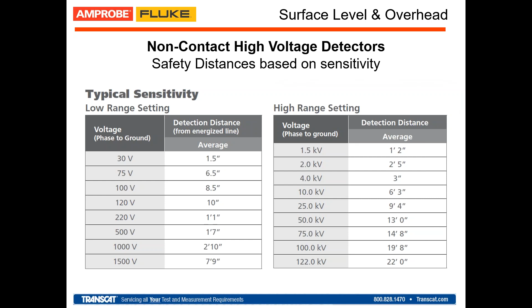So the NCVs are pretty straightforward tools, right? They're very, very intuitive, but we still see some customers that do and do not know what these tools do. The straightforward benefit of a high voltage non-contact detector is that they just don't make contact with the hot line. There are other voltage detectors in the market for high voltage that do make contact. Some of them provide just a yes or no voltage detection flag or light. Others provide the actual measurement of the voltage in that line. But regardless, you need to make contact with that equipment to the line.